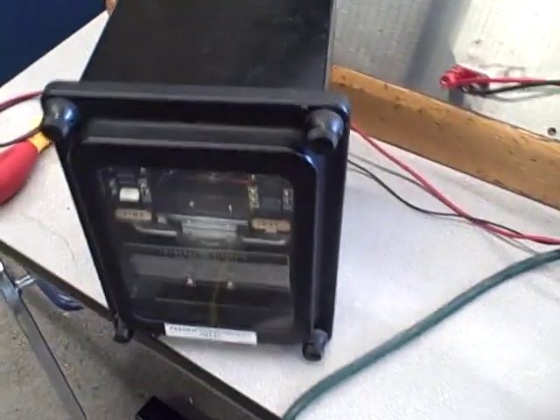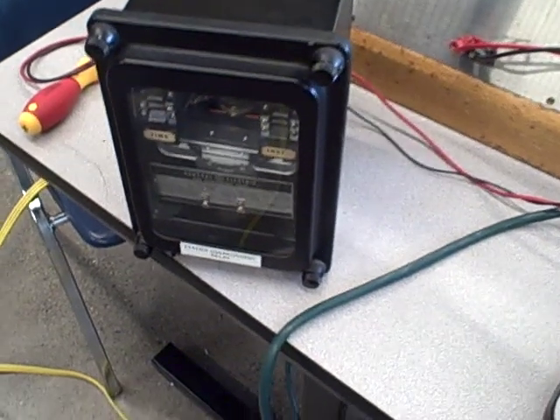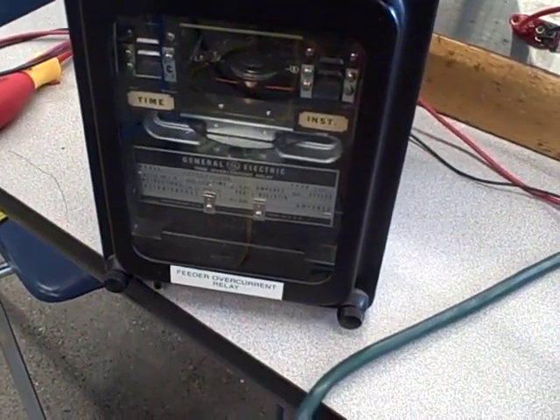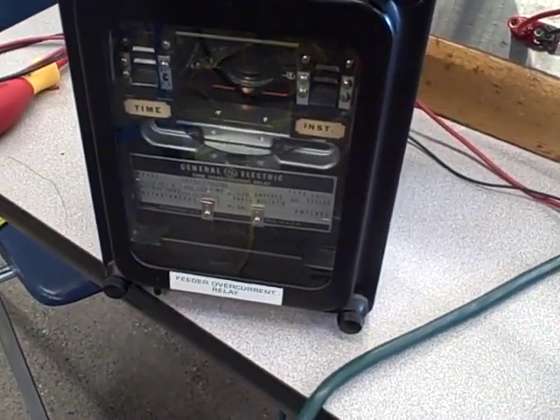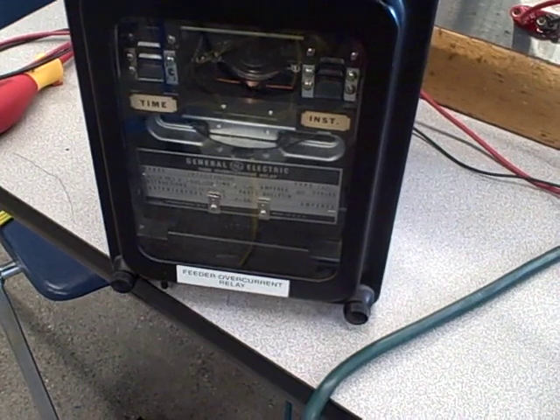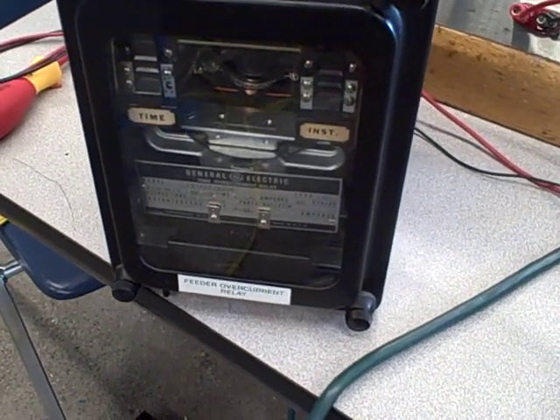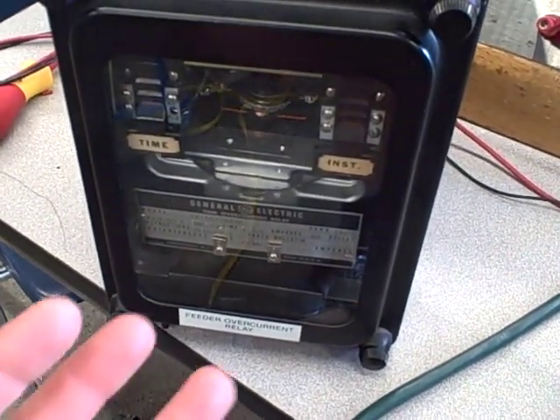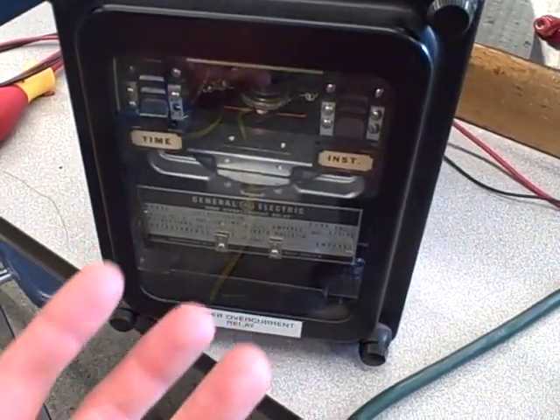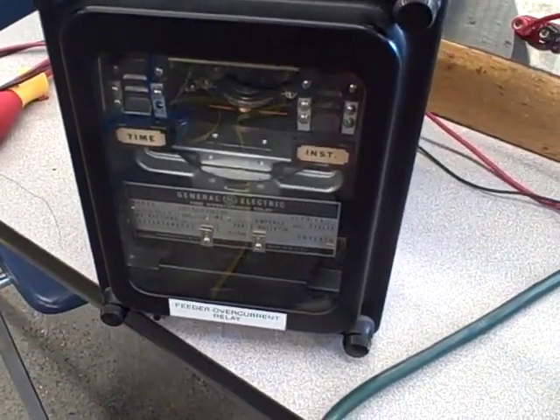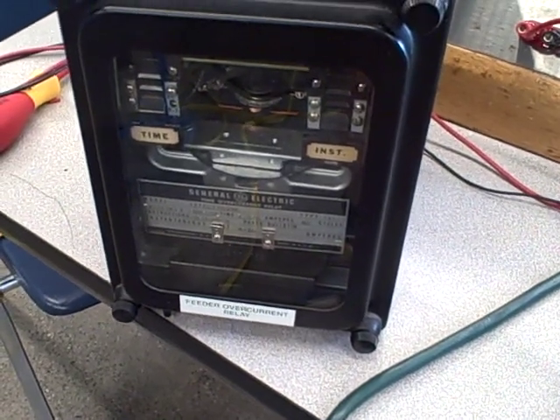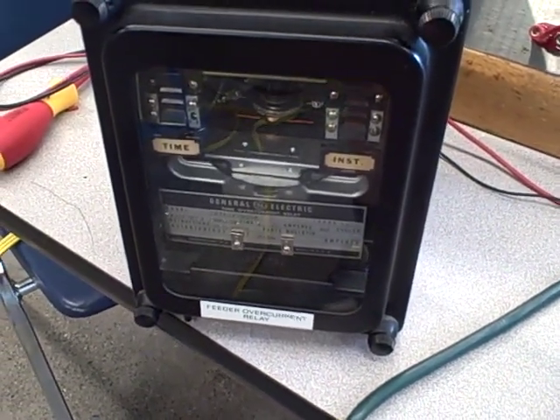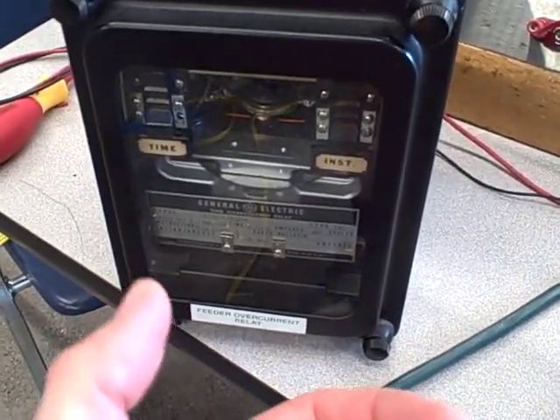What's neat about this is when you're doing tests like this on a protective relay, the time measurement, especially for high currents, how much time it takes to move that induction disc around and trip the relay, that time can be very difficult to measure with a hand-driven stopwatch.